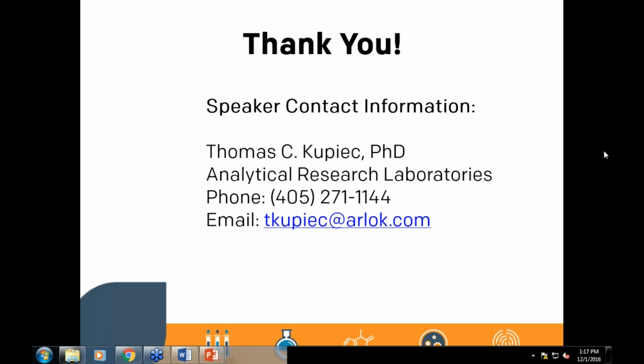I think that if you have the ability, and you have an HPLC, and you have the personnel that are adequately trained, you have the equipment that's operating appropriately, and you understand the conditions, and you have the processes and knowledge, then it can be performed. There's no one saying it has to be done in a lab.